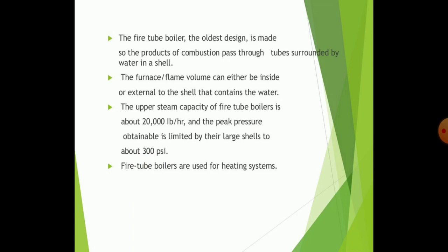Fire tube boilers are the oldest design type. In them, combustion gases pass through tubes surrounded by water inside the shell. The furnace or flame volume can either be inside or external to the shell that contains the water. The upper steam capacity of a fire tube boiler is about 20,000 pounds per hour, and the peak pressure obtainable is limited by the large shell to about 300 pounds. Fire tube boilers are used for heating systems and particularly for steam generation with a moderate rate of heat transfer.